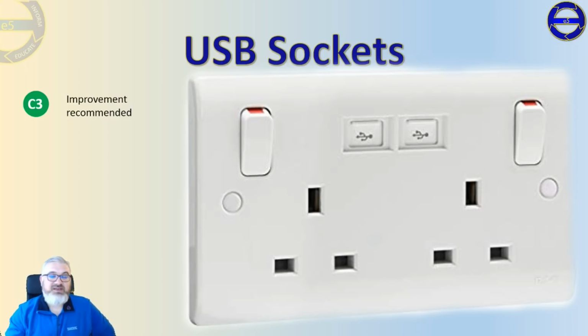Now, if I was an inspector, you see above me, C3, improvement recommendation, and all the sparks go, what? No, you cannot code a socket outlet that doesn't have a scribble on it. Well, that's down to the inspector. If I was inspecting a fixed installation, I would issue a C3 against the socket not complying with the standard. Now, under BS 7671, you only code what is in the wiring regulations. The wiring regulations don't cover that.